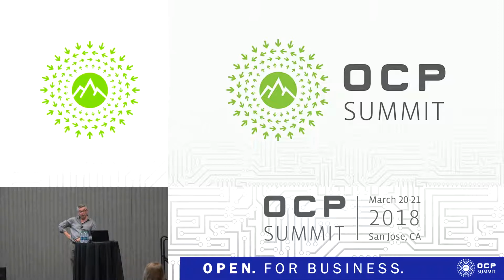Yeah. And then my second question was on your fault alerts. One of the ones I noticed was incompatible rectifier type. This whole presentation was about a 6 kilowatt rectifier. Do you have a form-fit compatible other size rectifier, like 3 kilowatts or 2 kilowatts? In this form factor, no. We have others in other applications. We have some 24 and 48 volt rectifiers which are physically the same form factor. And if you were plugging one of those into the others, that's exactly the alarm that you would see.